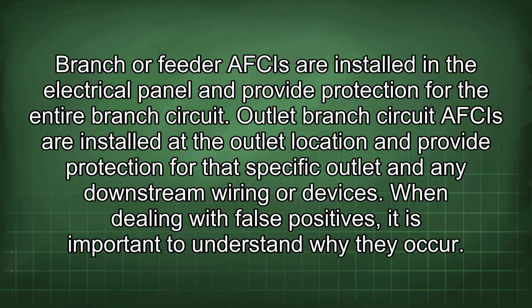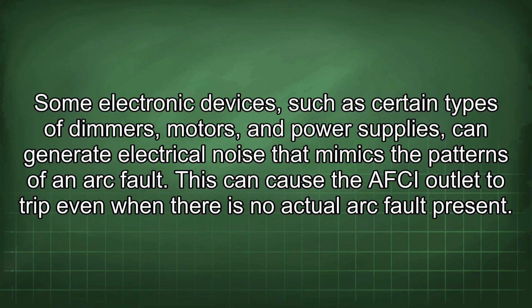Branch or feeder AFCIs are installed in the electrical panel and provide protection for the entire branch circuit. Outlet branch circuit AFCIs are installed at the outlet location and provide protection for the specific outlet and any downstream wiring or devices. When dealing with false positives, it is important to understand why they occur. Some electronic devices, such as certain types of dimmers, motors, and power supplies, can generate electrical noise that mimics the patterns of an arc fault. This can cause the AFCI outlet to trip even when there is no actual arc fault present.